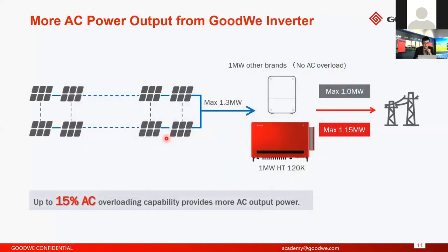And here's AC overload. For our product, maximum we can support 15% AC overloading on the AC side. So that means, for example, here you can find this slide. For example, if the inverter capacity is 1 megawatt, but on the DC side, maximum the inverter can output 1.15 megawatt on the AC side. So we can get more generation on the AC side.